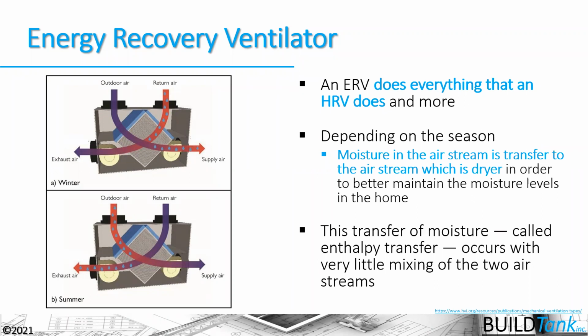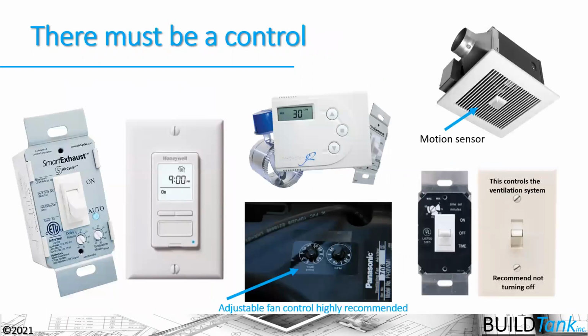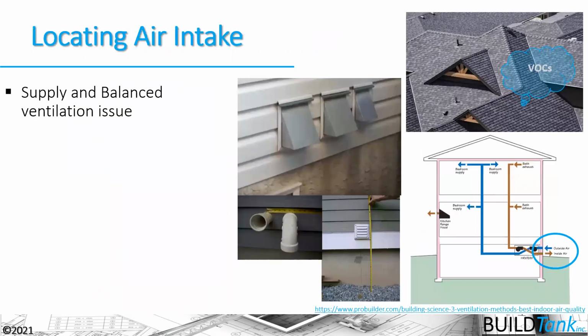Although energy recovery ventilators can be used in cold climates and dry climates, heat recovery ventilators should not be used in humid climates down south, for example. Regardless of the system that you use, you need to have that control. That's a requirement of the code, so you can turn it off during pollution times like smoke or car pollution that might be going on. And those controls now must be labeled.